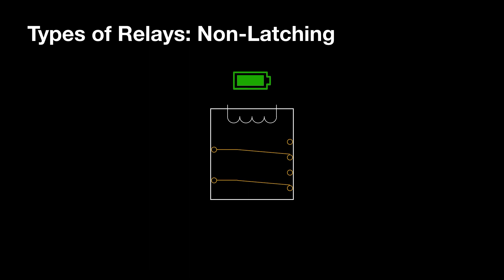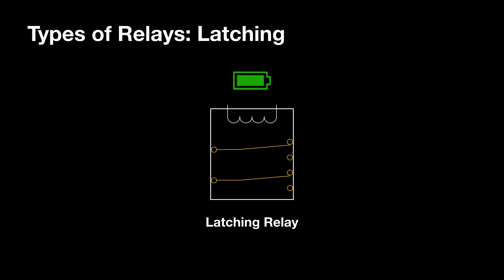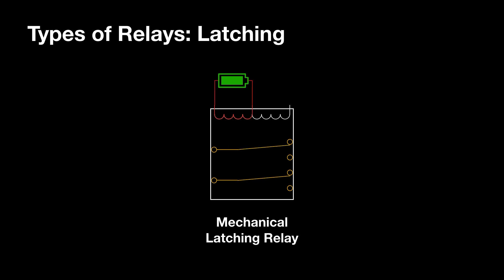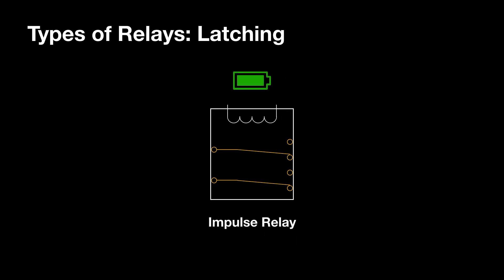For the next type of relay, the armature does not return to its resting position when power is removed from the coil. This is what is known as a latching relay. There are three main types of latching relay. The first type requires the polarity of power applied to the coil to be reversed to get it to return to its original position. The next type is called a mechanical latching relay — it has two coils, one to move the armature one direction and the other to move it back. The final type is called an impulse relay, where the armature will switch states each time power is applied to it. These relays can be used to save energy because they don't require the coil to be powered to hold the relay in a particular state.